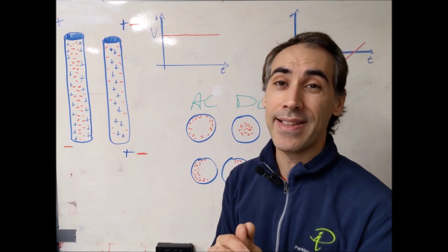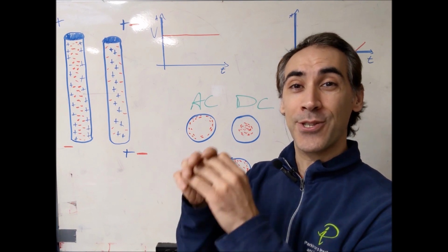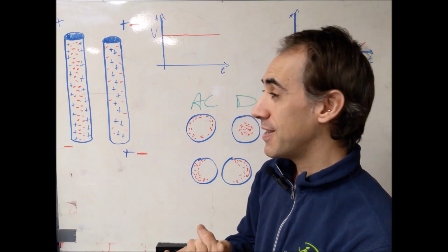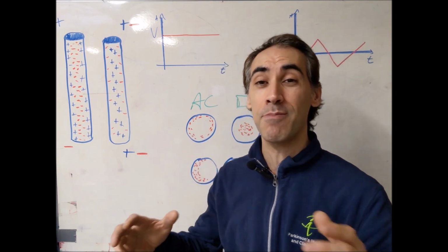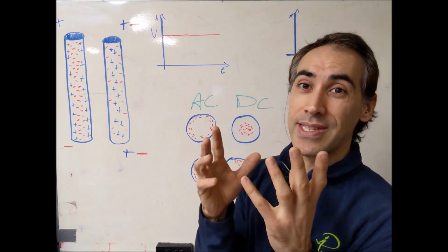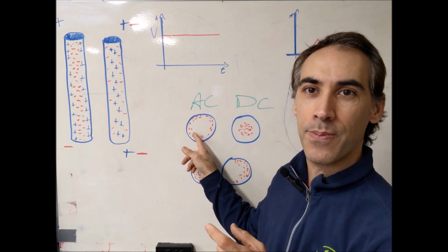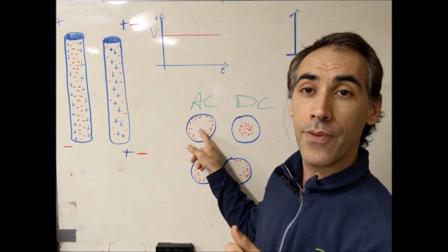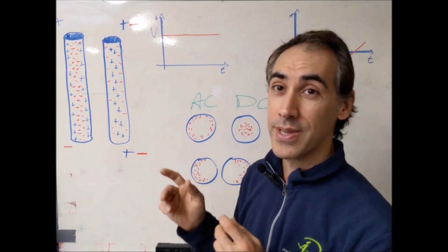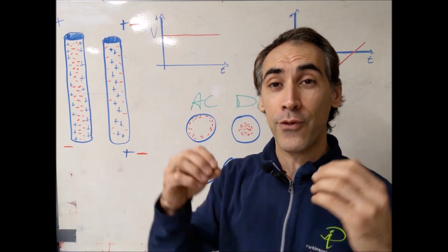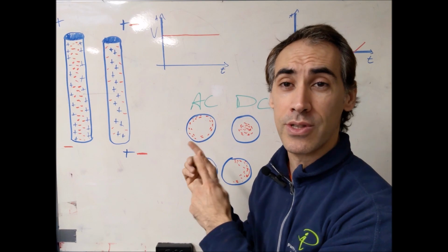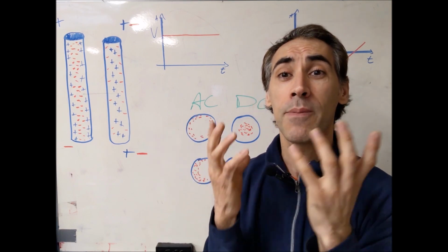We have a skin effect, as mentioned before, on the AC. The charge itself prefers to travel outside our conductor. The higher the frequency, the more the skin effect is present and visible. Whenever we have a skin effect, we have an unutilized piece of volume inside the cable. So that is the problem. You need to size up the cable in order for this charge to have more surface and volume around the conductor. Otherwise, this conductor can really heat up and cause big problems.